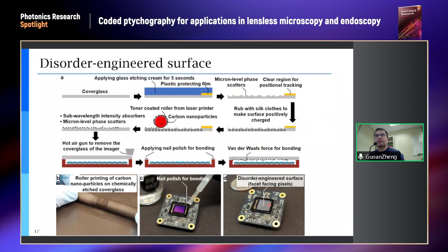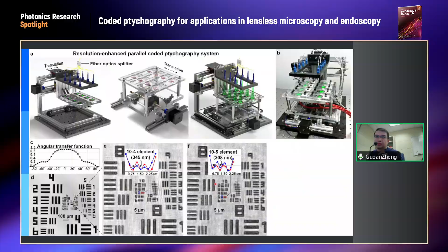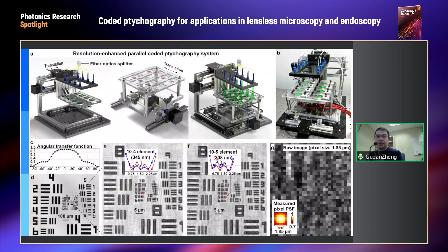With this device, we build a parallel imaging platform. We put a coded sensor here, and we can image multiple samples at once. This is the prototype device. This is the recovered image using this lensless imaging platform. This is the recovered image of the resolution target using green light. This is the recovered image using blue light. We can also show you the corresponding diffraction pattern we captured. You can see that the pixel size here is about 2 micron. And from the reconstruction, we can resolve a 300 nanometer line width from this resolution target.